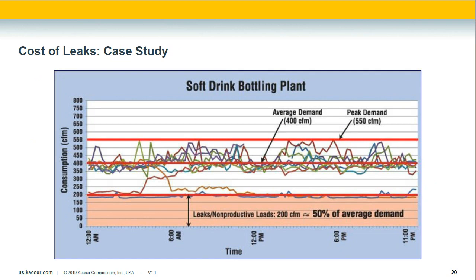In a case study, a soft drink bottling plant was losing about 200 CFM to leaks and nonproductive demands — nights, weekends, and off-shift — resulting in $34,000 per year of wasted energy. This data quantifies the leak rate for the customer and provides real impetus to conduct a leak study, showing the power of a compressed air audit.